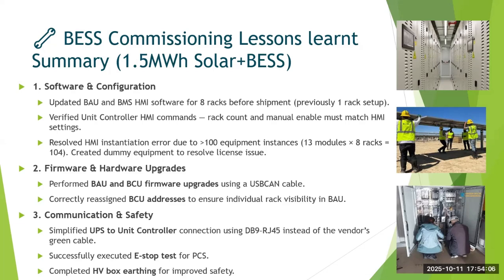In the firmware of the BCU, all the addresses were given as 1. So what was happening is we have 8 racks, but the BAU was understanding only 1 rack because all the addresses were the same. Then I had to go and hook up to the BCU with a cable and change the address of the BCU in the firmware, so that the BAU would be able to understand, for each BCU, what address is given. We did all this practically at the site. Whereas if we had all the BAU and BCU firmwares, everything, configured in the factory before shipment, all this could have been avoided in commissioning.